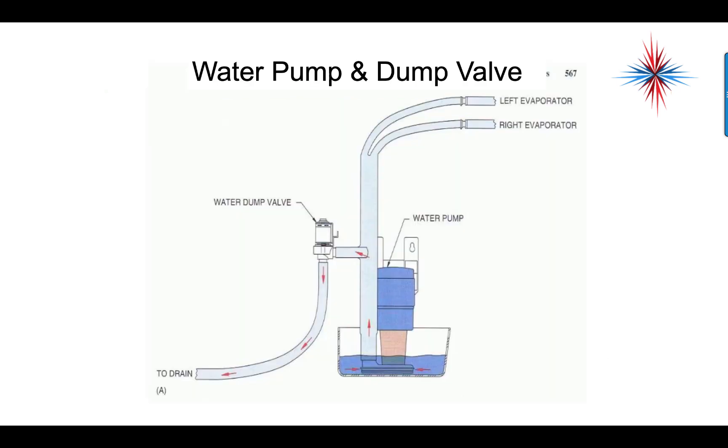The water dump actually works by basically a valve opens. The pump still is running, but the water gets diverted out the dump valve because the water will take the path of least resistance. As long as the water dump valve is lower to the drain than the evaporator panels, the water will run out of the dump valve.